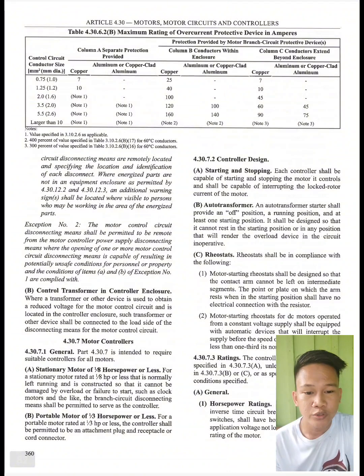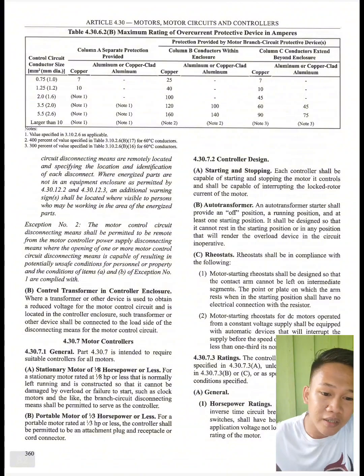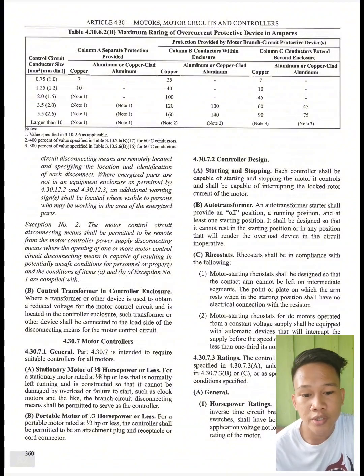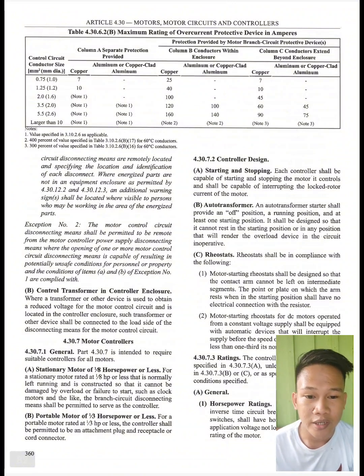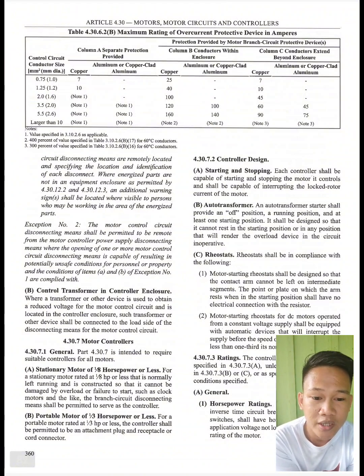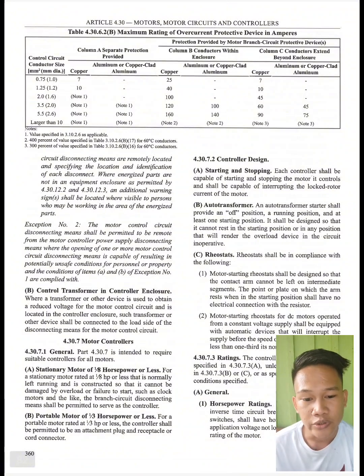So we have here 4.30.7, motor controllers. 4.30.7.1, General. Part 4.30.7 is intended to require suitable controllers for all motors. First, we have stationary motor of 1/8 horsepower or less. For a stationary motor rated at 1/8 horsepower or less that is normally left running and is constructed so that it cannot be damaged by overload or failure to start, such as clock motors and the like, the branch circuit disconnecting means shall be permitted to serve as the controller.